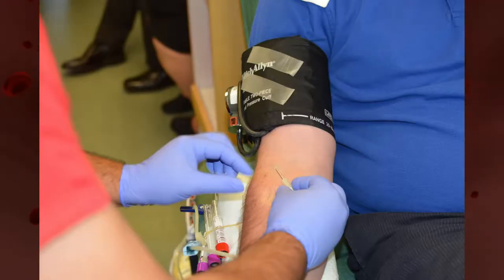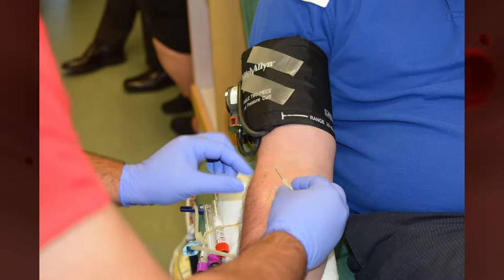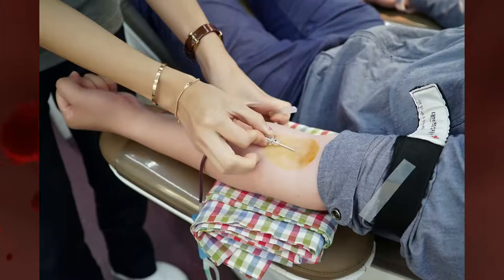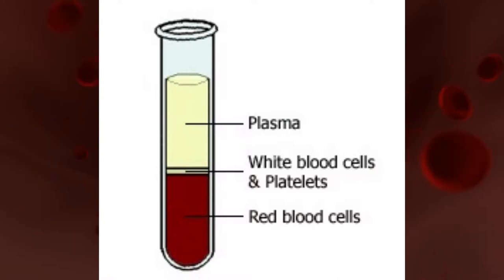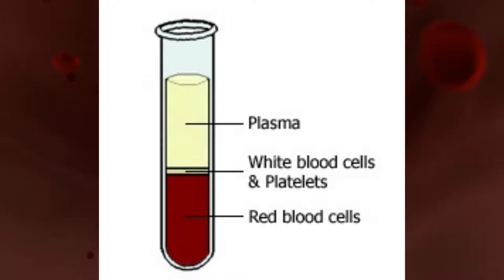First, you are set up as per normal with a blood donation. The only difference is that they use a slightly larger and differently designed catheter. The catheter in the vein begins by taking out the whole blood, which enters a centrifuge rather than a donation blood bag. In the centrifuge, the whole blood is spun, which forces the erythrocytes, leukocytes and plasma to separate. The plasma is then drawn off and put into the plasma bag.